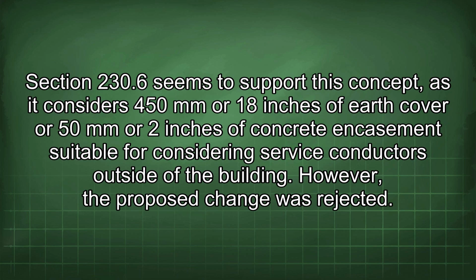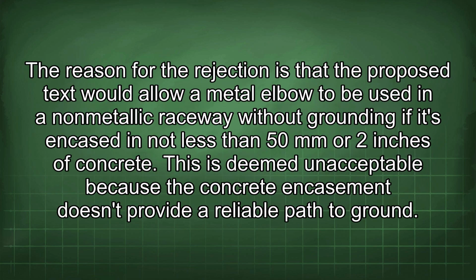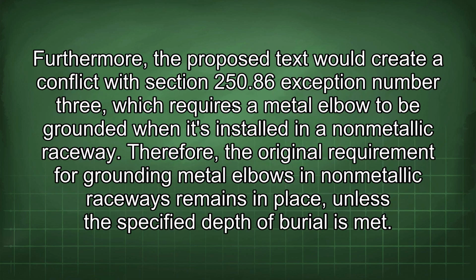Section 230.6 seems to support this concept, as it considers 450 mm or 18 inches of earth cover or 50 mm or 2 inches of concrete encasement suitable for considering service conductors outside of the building. However, the proposed change was rejected. The reason for the rejection is that the proposed text would allow a metal elbow to be used in a non-metallic raceway without grounding if it's encased in not less than 50 mm or 2 inches of concrete. This is deemed unacceptable because the concrete encasement doesn't provide a reliable path to ground. Furthermore, the proposed text would create a conflict with section 250.86 exception number 3, which requires a metal elbow to be grounded when it's installed in a non-metallic raceway.